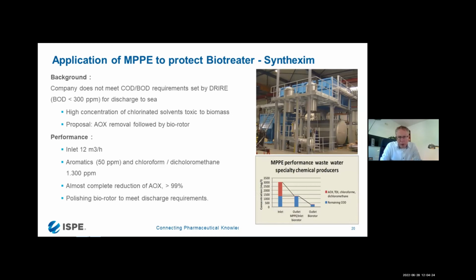Another example from the industry is that we ran into a client that was not able to treat their wastewater according to the requirements that were set by the local authorities. In this case, the BOD, the biological oxygen demand of the wastewater, should be less than 300 ppm in order to discharge it to the sea. And the client was not able to meet it.